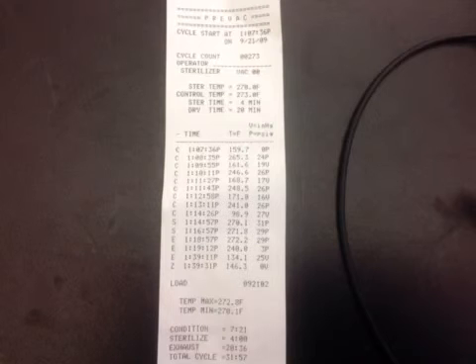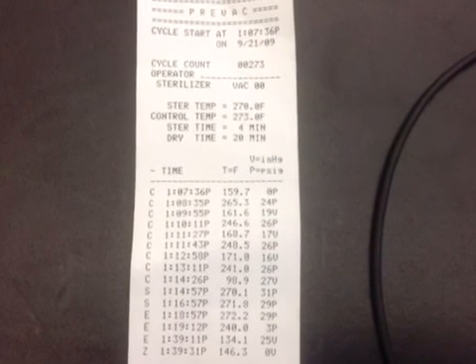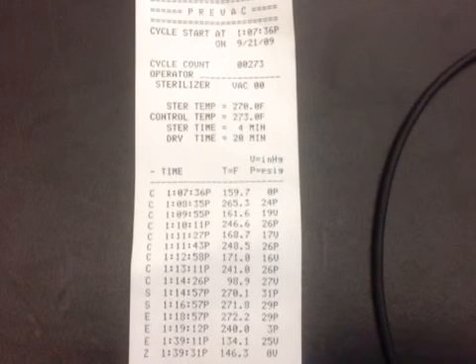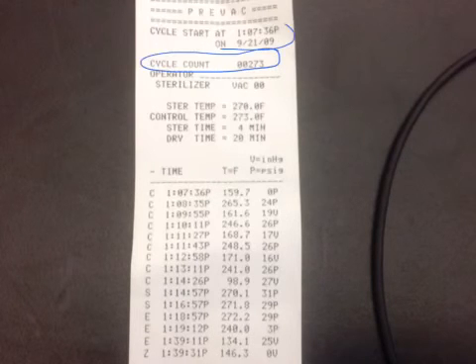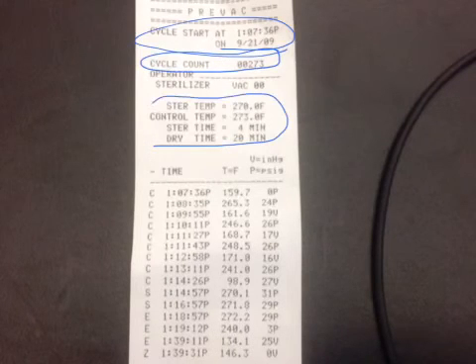This third one is a prevac cycle. Prevac is typically used for drills, something that we need to get good penetration. We'll start out here again. We have our cycle count number, date and time. Here in our summary, we said this is a 4-minute sterilization and a 20-minute dry time. A 4-minute prevac can sterilize many items, but there's a 20-minute dry time typically connected with that.